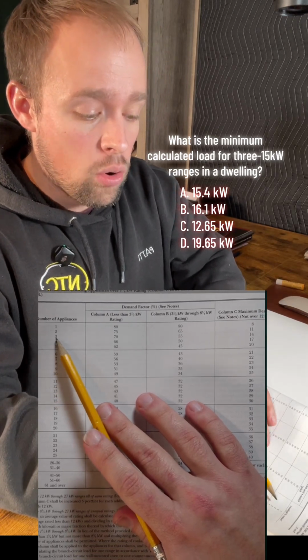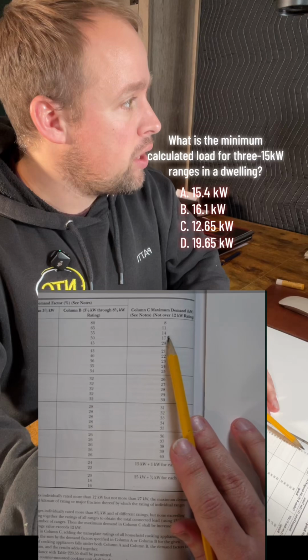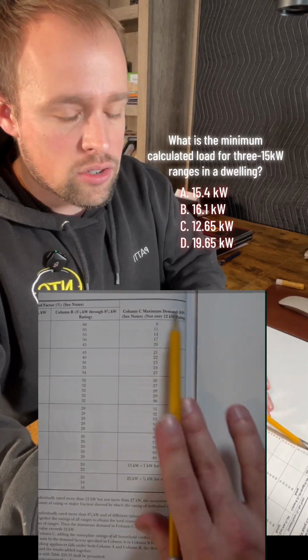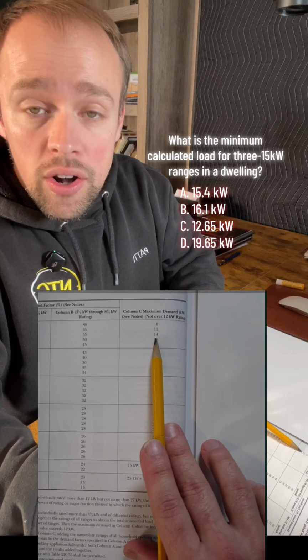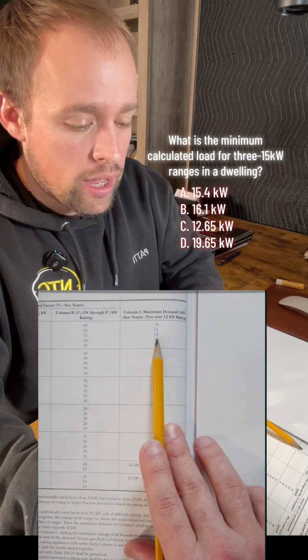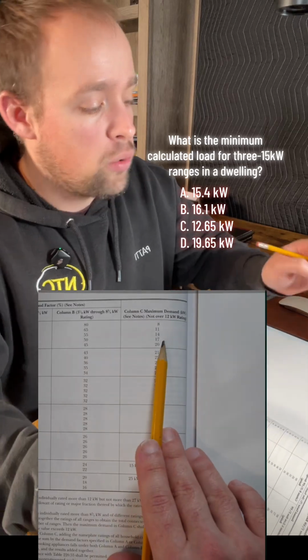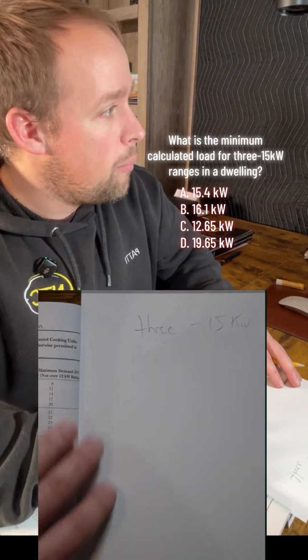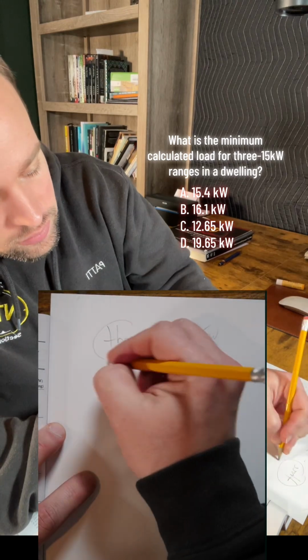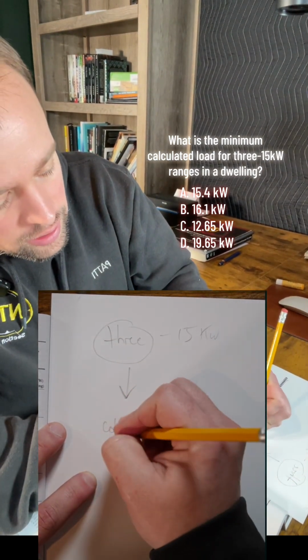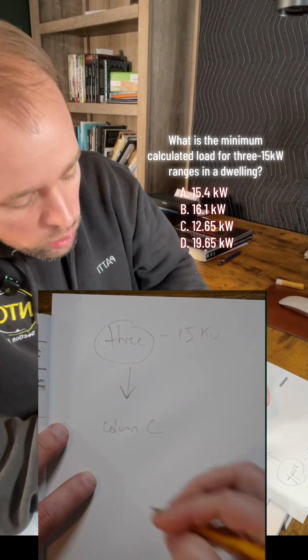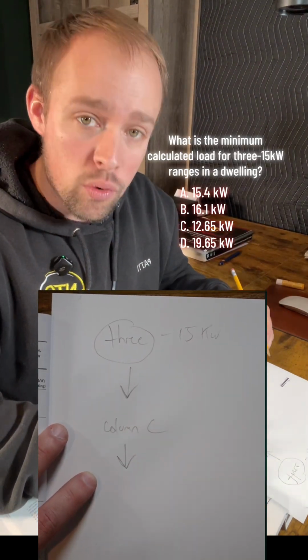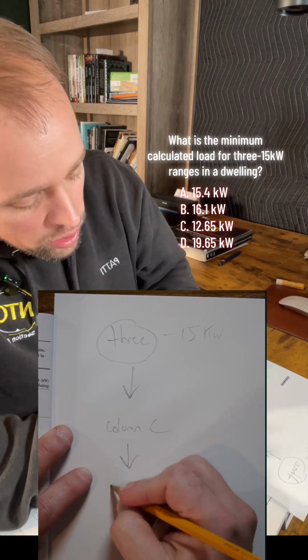So we're gonna go over to column C. When 3 appliances fall under the circumstances in column C, we're starting with 14 kW. So again, the number of appliances in question give us a column C value. What is that value? Just like I said, it's 14 kW in accordance with column C.